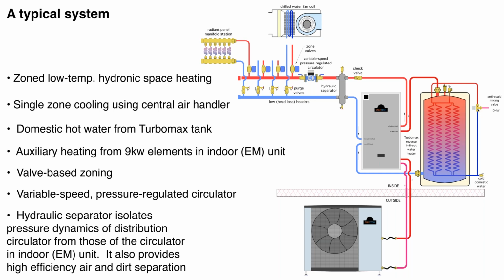It would prevent water at temperatures over 120 degrees, which is typical, from going to the fixtures, okay? So that's the overall system there, and it brings together many state-of-the-art components like high-efficiency circulators and the hydraulic separator and the high-performance TurboMax indirect water heater, okay? The electric version of the heat pump also has built-in 9 kilowatts of electric resistance heat. So it has its own built-in auxiliary heating system.